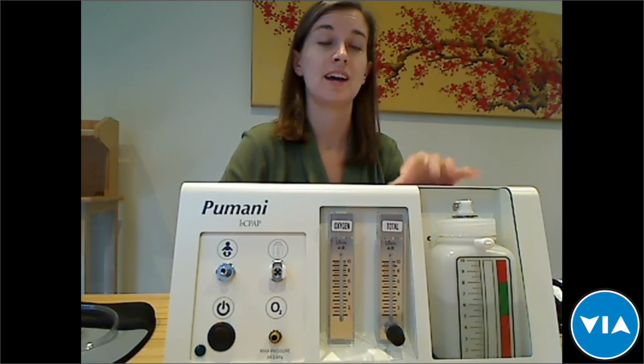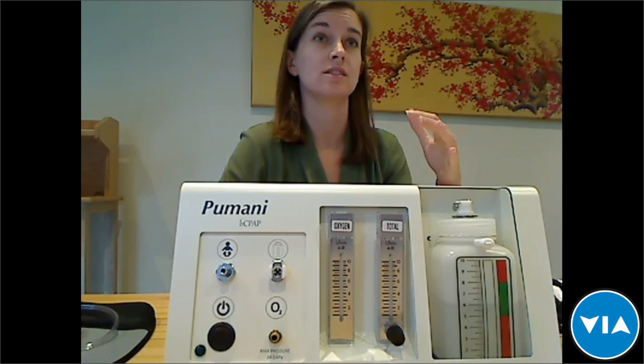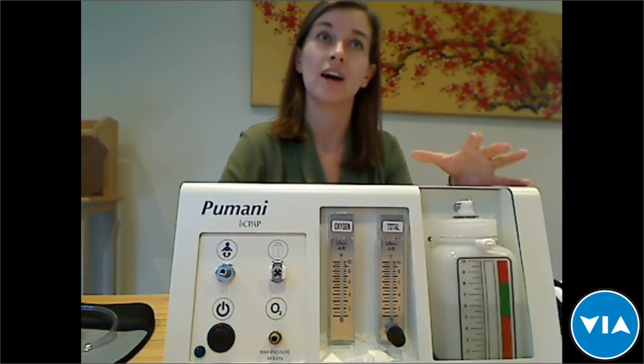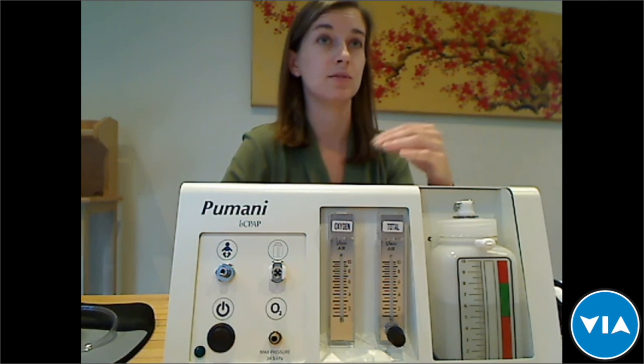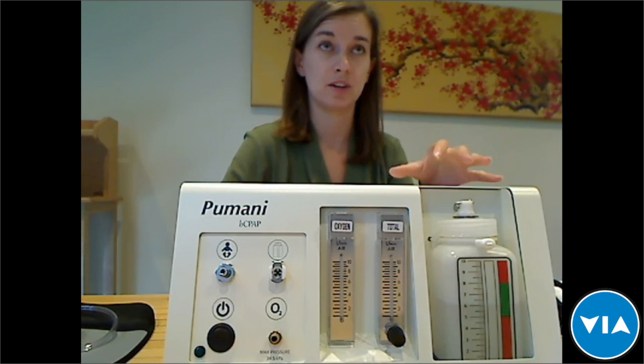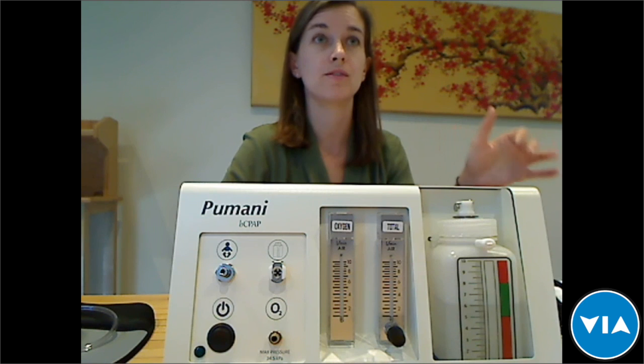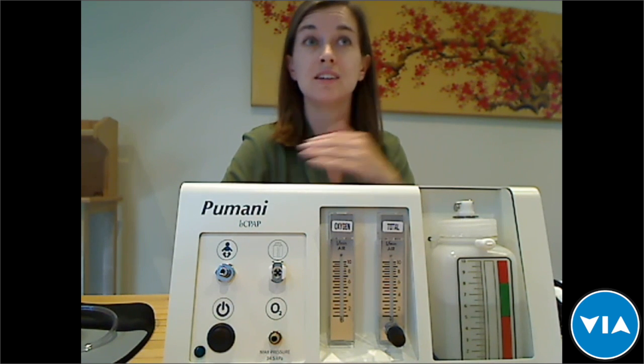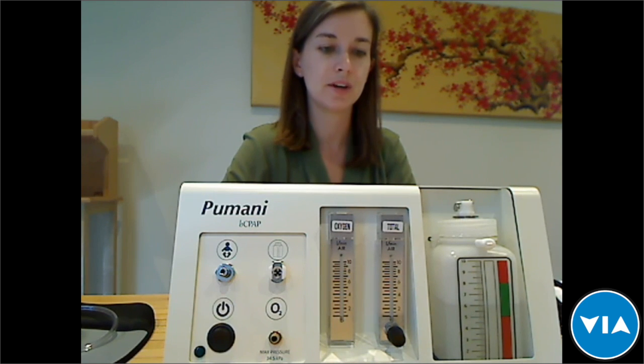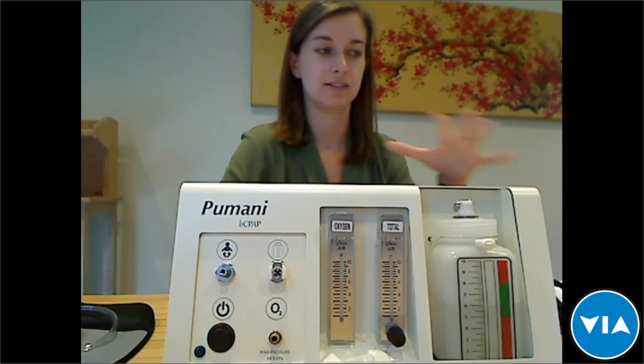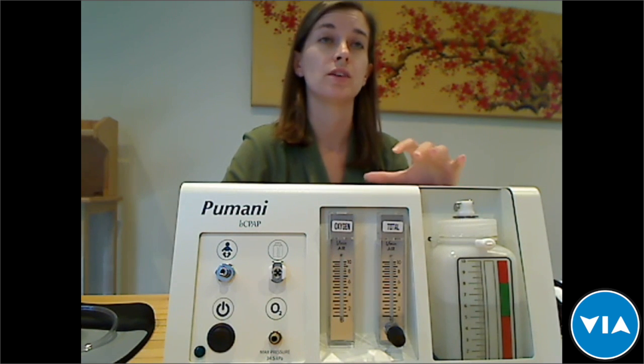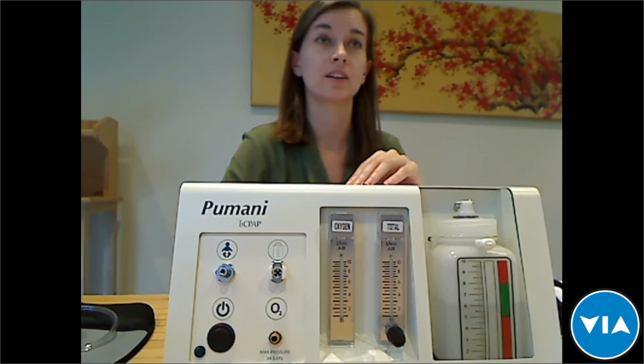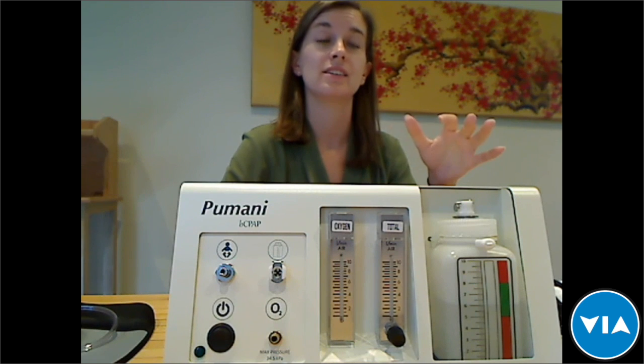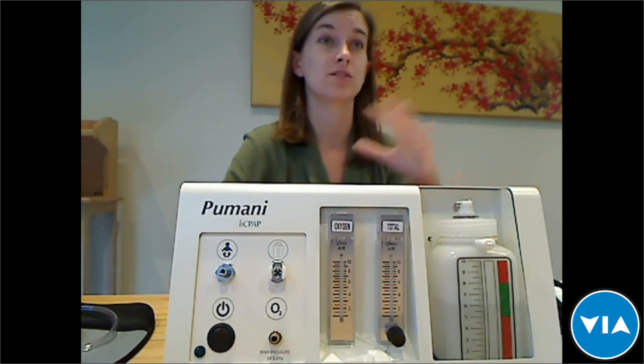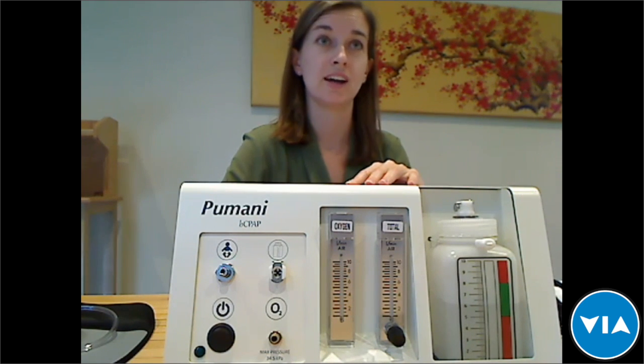And our compressor, I should also say, has been upgraded several times to ensure its longevity. We originally used a low-cost diaphragm pump that worked for several years continuously, but we found a pump that was very similar but even more durable, and we've since replaced the previous pump with this new pump, and now the lifetime should be at least 5 years, if not longer. And I believe this device has been in design and development for over 5 years, working very closely with Malawian nurses, pediatricians, clinical officers, the Ministry of Health, and they really had a significant contribution to the design and the development and the training materials as well. And so it's really been designed specifically for these users and with these users.